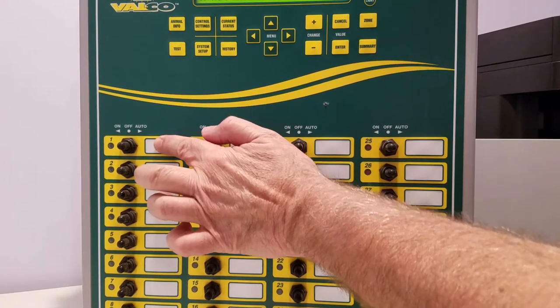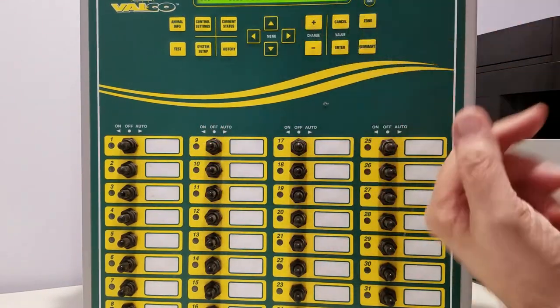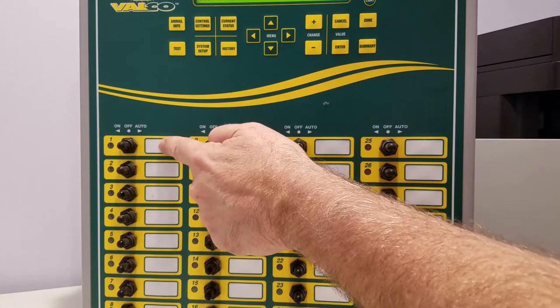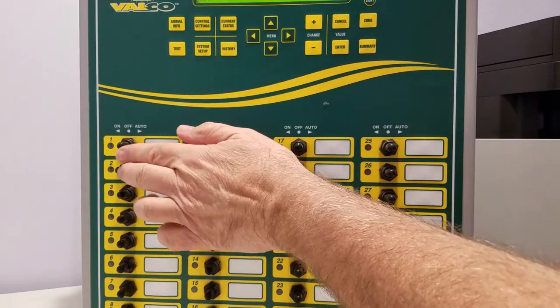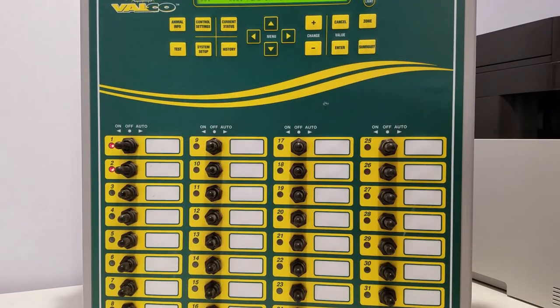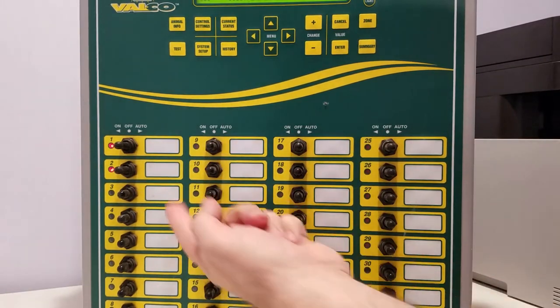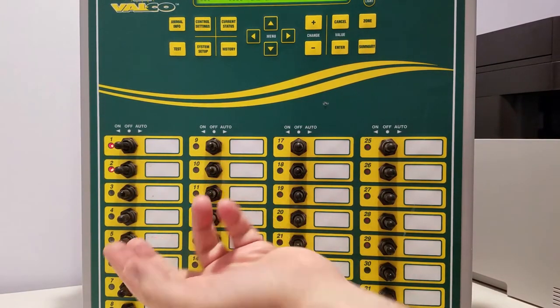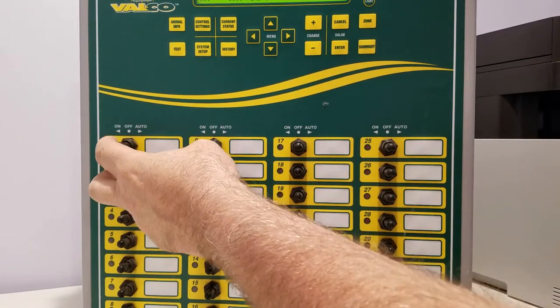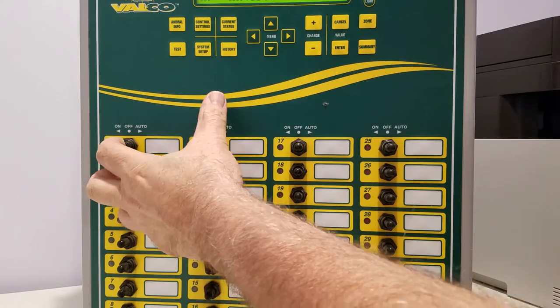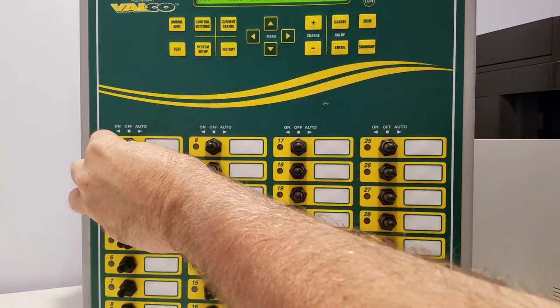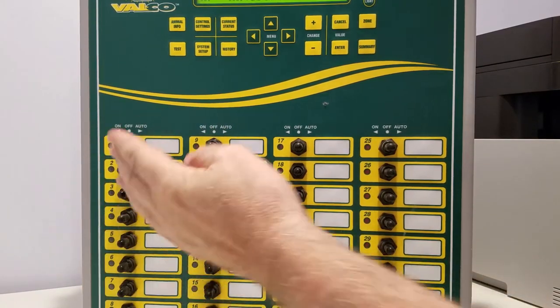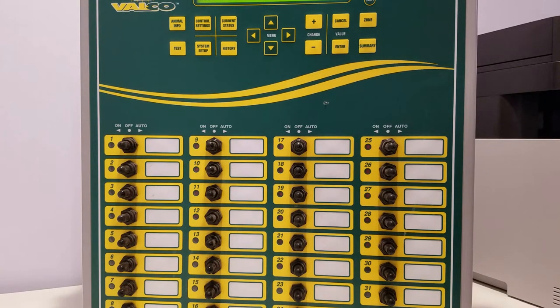So in this example, got a sidewall inlet here on channel one. If somebody flips both the open and close channel one and channel two on, they're both going to try to run. The motor will sit there and hum and get hot and it's not going to operate correctly. In the software logic, it won't allow that kind of conflict when everything's running in auto, but in manual you could have an issue.